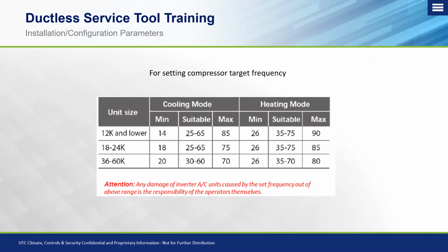This is more so for just figuring out where that actual point is. And then, of course, if something does need to be changed, that is either going to be communicated and approved by myself or someone directly at the factory, depending on the situation that we're dealing with. But they do list this in the manual for you to realize what a suitable range is. So if you're trying to adjust the frequency to a certain point while testing an individual component, you want to make sure you keep that setting between the suitable range so you don't cause any harmonic damage from the compressor overspeeding itself.